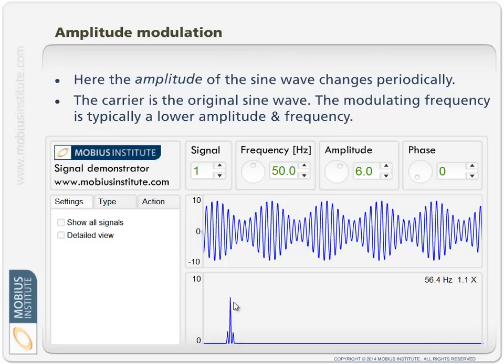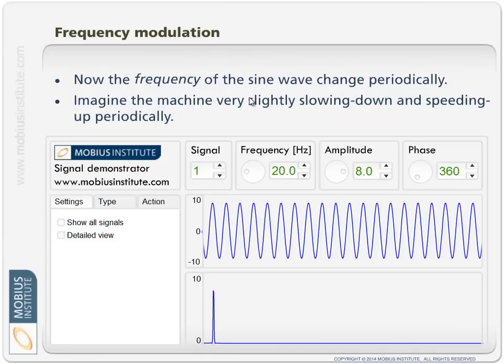So when you look at it, you might see a peak and think, wow, it's not an integer multiple of running speed, I don't know what it is. But you might find that if you subtracted twice line frequency, there might be a small peak in the spectrum, and that would be an integer multiple of running speed. It would be the number of rotor bars. Anyway, so we can see various combinations of these sorts of things, which we'll explore a little bit in just a second. So that is amplitude modulation, and shortly I'll just summarize a few things regarding the sidebands.